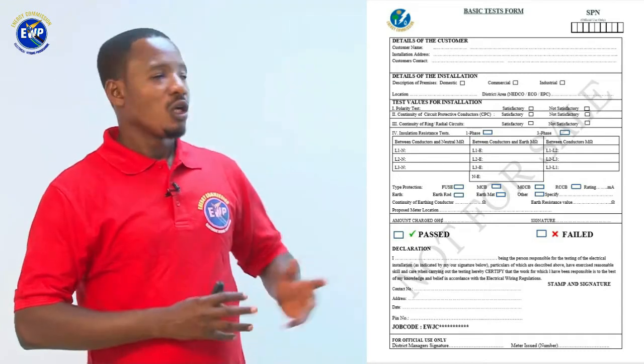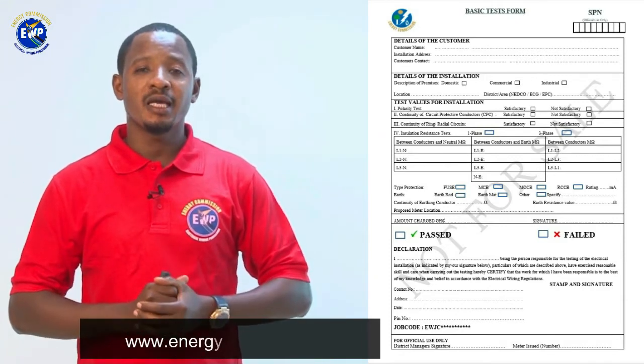In summary, you can obtain the basic test form from the Energy Commission's website, and then make sure that the details of client you indicated on the form A is same as on the basic test form. On details of the installation, you are required to indicate whether it's a domestic, commercial, or industrial, and then to indicate the location where the facility is located, and then the ECG or NEDCO district within which the facility falls. You are required to carry out a series of tests from polarity test, continuity of circuit protective conductor, continuity of ring or radial circuit, and then insulation resistance test and your earth electrode resistance test, and record the values accordingly.